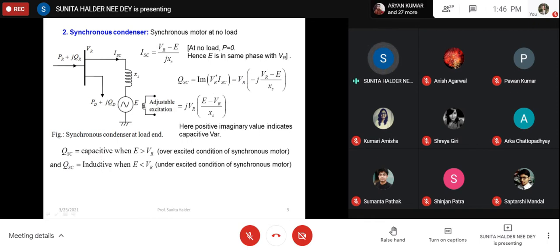So a synchronous condenser at no load, we can operate by controlling the excitation, we can make it capacitive, make it absorb capacitive var as well as inductive var. So both purposes may be served using the synchronous condenser. So it is very easy to switch from the capacitive mode to the inductive mode. Only the thing is that it is very costly, since it is a rotating machine, its maintenance cost is high and its installation cost is also high as compared to the conventional capacitor.